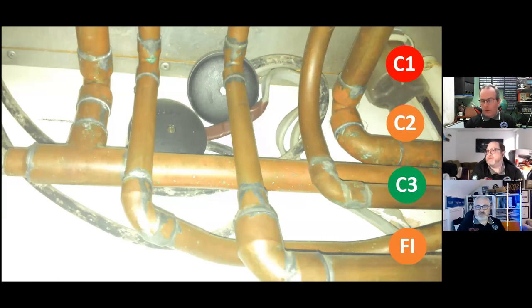Okay, so we've got issues with access. Those cables have definitely been exposed to external influences that potentially could have damaged them. Is that scorching or are they mouldy? I was told it was scorching. It's quite uniform over the whole length of the cable. Yeah, well, that's plumbers for you. You could look at that as mould. Actually, I was told it was scorching, but yeah, you could suggest that could be mould. And it is uniform, in a boiler cupboard where it's going to be damp and all the rest of it. I actually would.